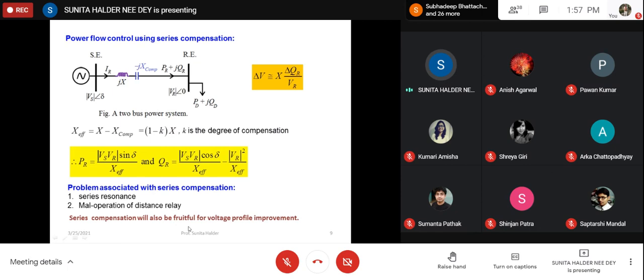Now, series compensation obviously will be fruitful for voltage profile improvement also. I shall teach you voltage control in the next class. In short, there are two types of compensation: one is series, another is shunt. Shunt is very easy. Locally, you can do it at the point where it is required. You insert either a capacitor or an inductor in the conventional mode, or if we want automatic control, we can use a synchronous condenser or the static VAR compensator, SVC. Series compensation is used to control the power transfer through a transmission line, to control the active power. Because if we increase the active power, then we can get more revenue, and the purpose of the transmission line is to transfer active power. All the things are the result of that. So the main purpose of series compensation is to improve power transfer through a transmission line.